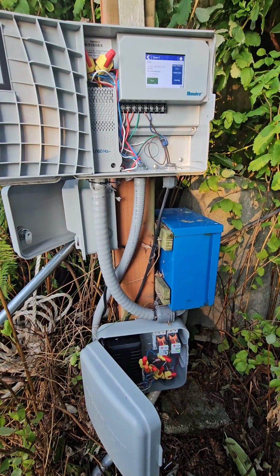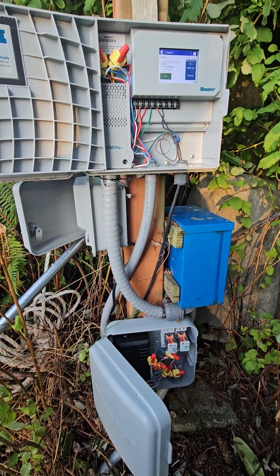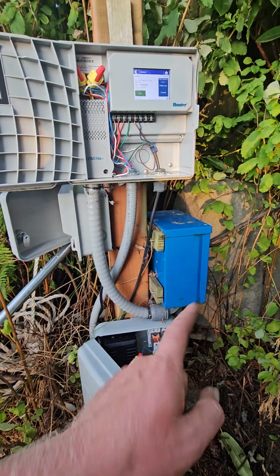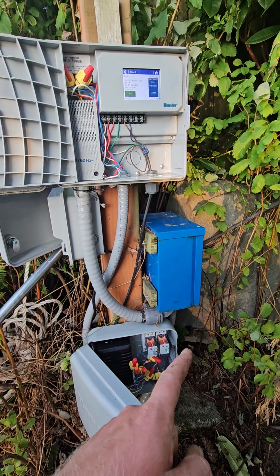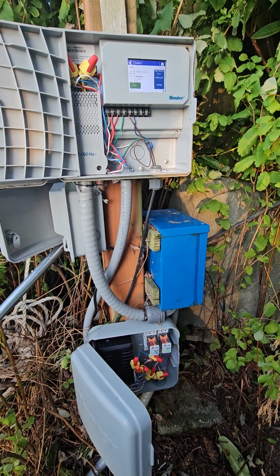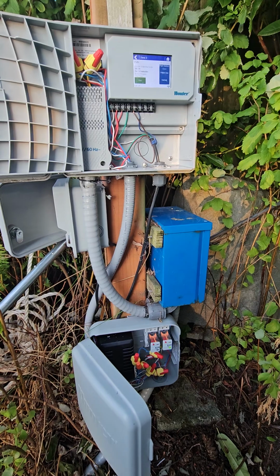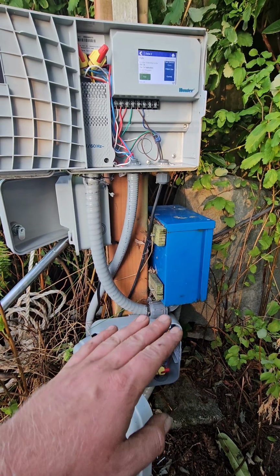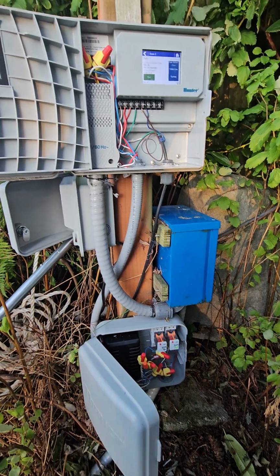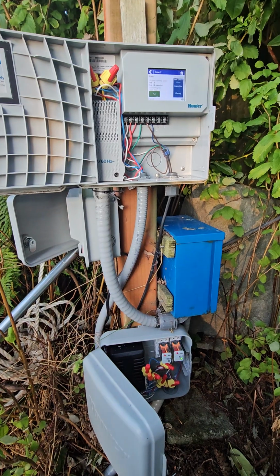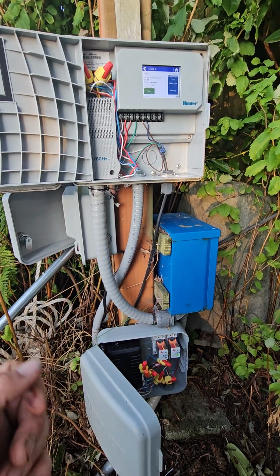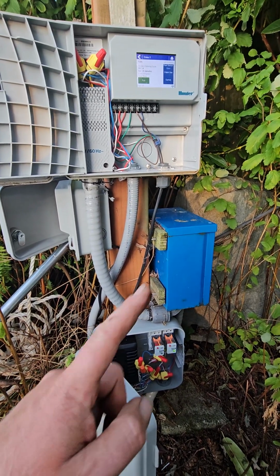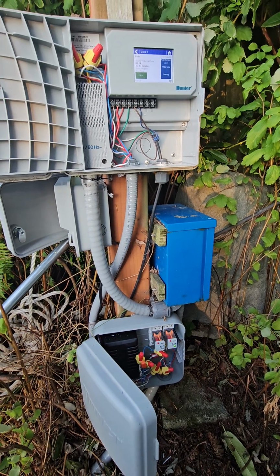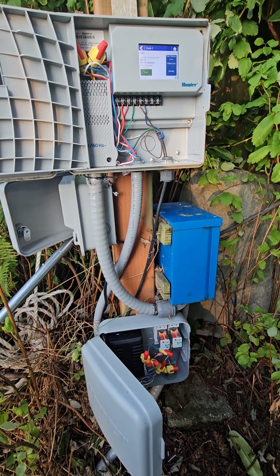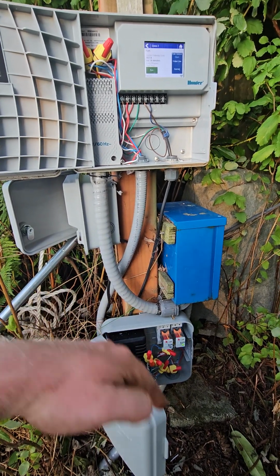Okay, so I don't do very many long form videos, but what we have is a 1.5 horse pump, and sorry, the squirrel in the tree. It's 115 volts, and the issue's been as soon as this pump turns on, the line voltage comes down to a point that this controller will just turn off or black out, and at the same time it will release the contactor and the pump never turns on, comes up to speed. But the pump will work if it can just get up to speed. So it's the inrush current that's drawing and pulling the line voltage down.